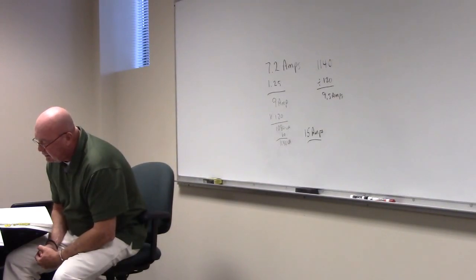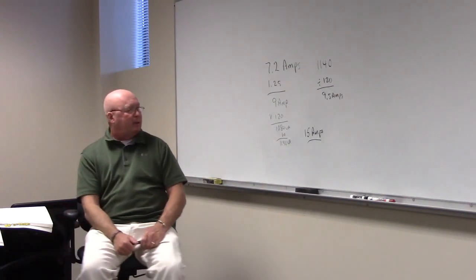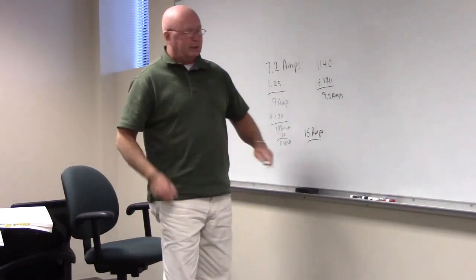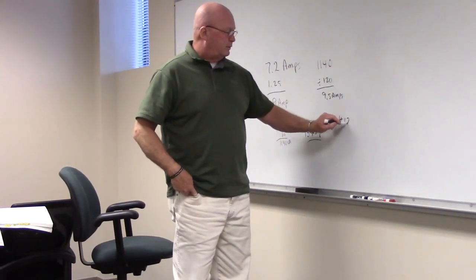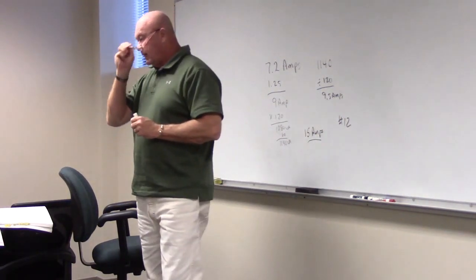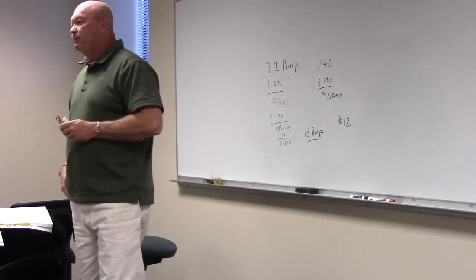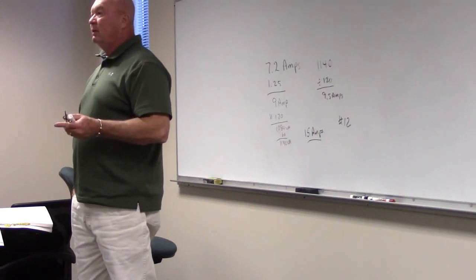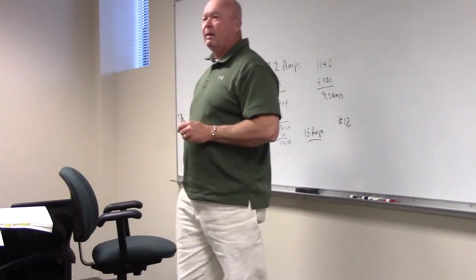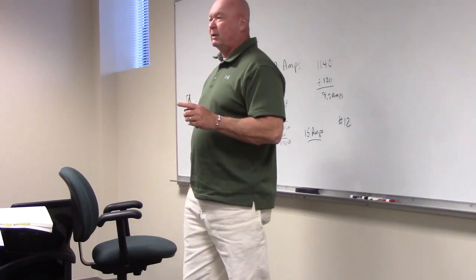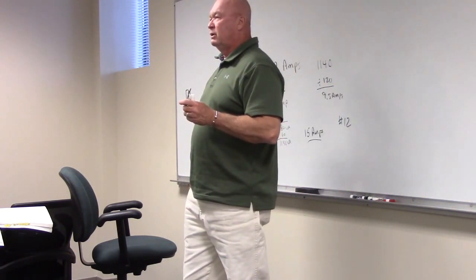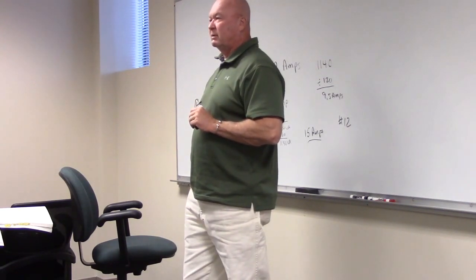15 amps. Look there in the book, what it says. The disconnect in this case would be 15 amps. Since the total connected load for the pump is less than 10 amps, a single branch circuit feeding the pump and the light switch will need only to be number 14. Number 14 copper, number 12 would be qualified service entrance conductors, because there is no minimum. But I can tell you what I would put, number 12, wouldn't y'all? Well, number 12 wire is good for what size circuit, as far as the NEC is concerned? 20 amps, isn't it? Even though a number 12 wire is actually good for how many amps? 30. Good for 30. The code book says what? The maximum you can use a number 12 for is 20 amps, right?